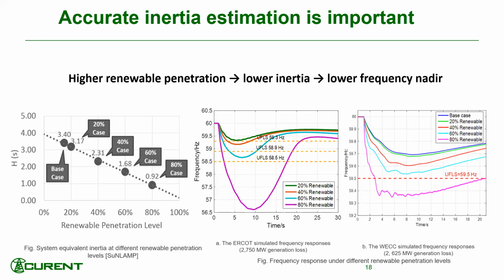However, if the grid starts to change quite a bit between different times of day—say at noon I'm mostly supplied by solar, and in the evening or morning hours I really have to crank up other generation—then my solar and wind may also be contributing to inertia if running in grid-forming mode, or my storage contributing to inertia in a grid-forming mode.